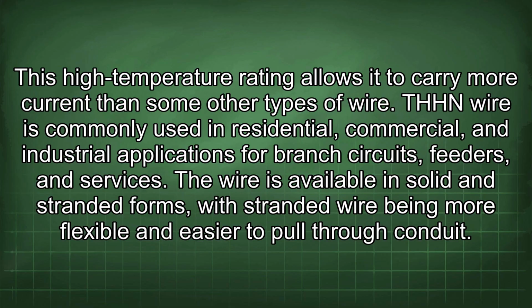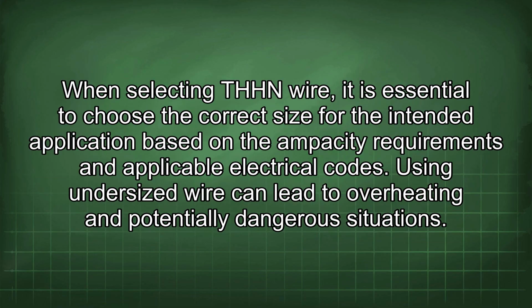THHN wire is commonly used in residential, commercial, and industrial applications for branch circuits, feeders, and services. The wire is available in solid and stranded forms, with stranded wire being more flexible and easier to pull through conduit. When selecting THHN wire, it is essential to choose the correct size for the intended application based on the ampacity requirements and applicable electrical codes. Using undersized wire can lead to overheating and potentially dangerous situations.